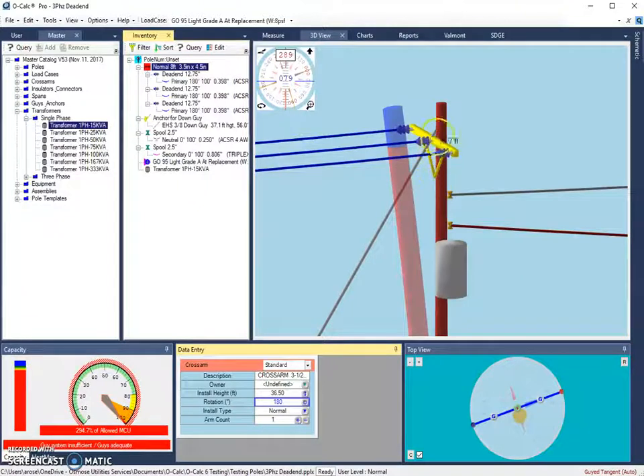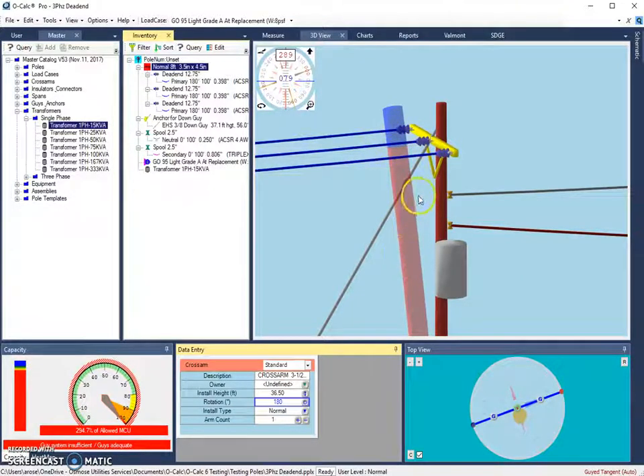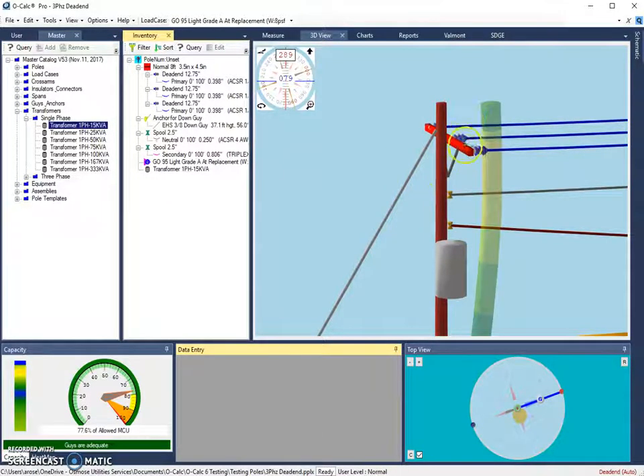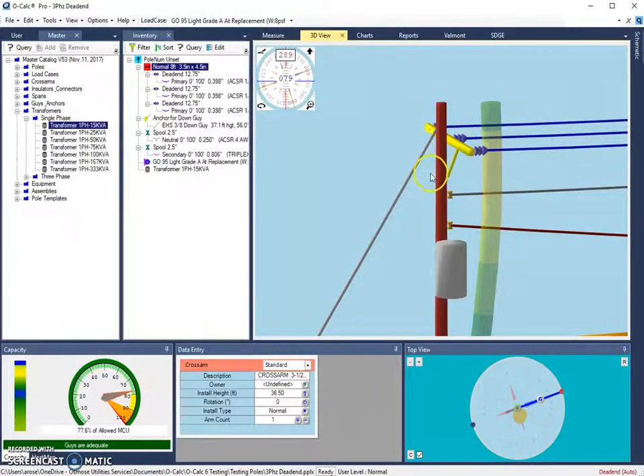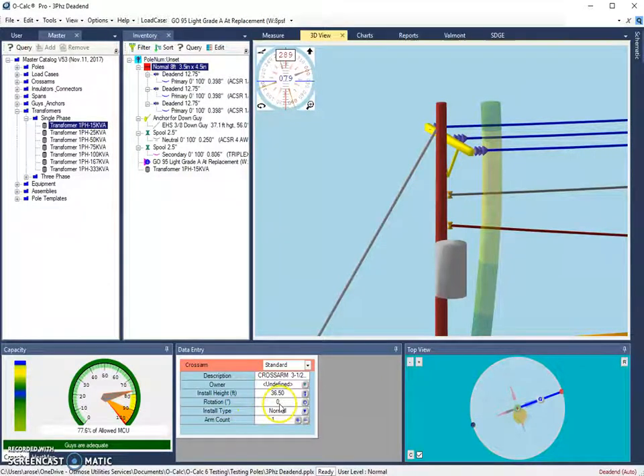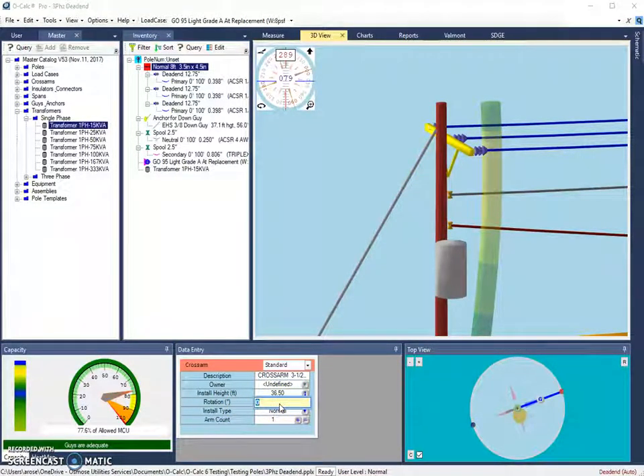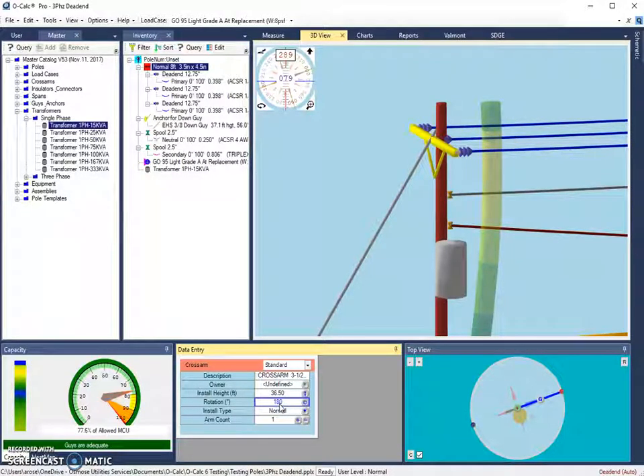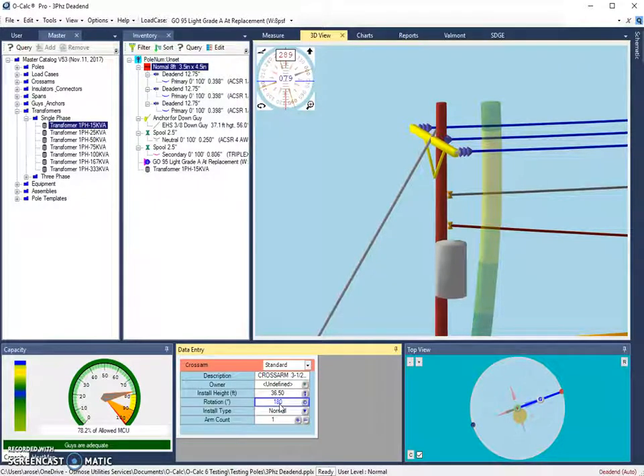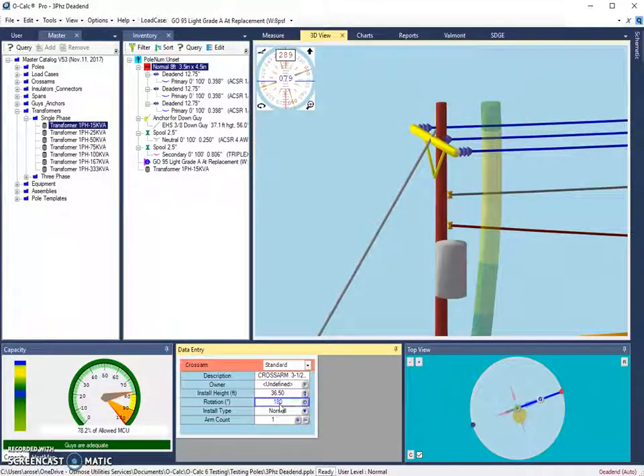This is because of the parent child relationship that exists here. So I'm going to do a control Z to undo that. Now, if I wanted to move just this cross arm to the backside of the pole, there is a shortcut to independently rotate an object. So I'm going to select my cross arm and go down to rotation where I'm going to use the IND shortcut. So IND equals 180 degrees, which will only rotate the cross arm 180 degrees. And that rotation does not carry down to all of the child items.